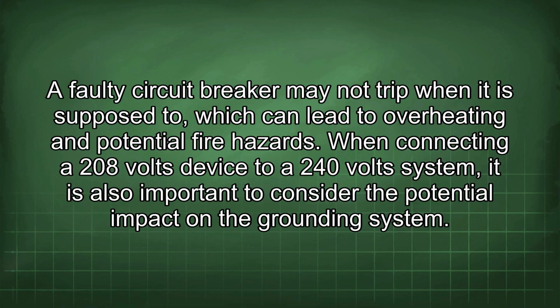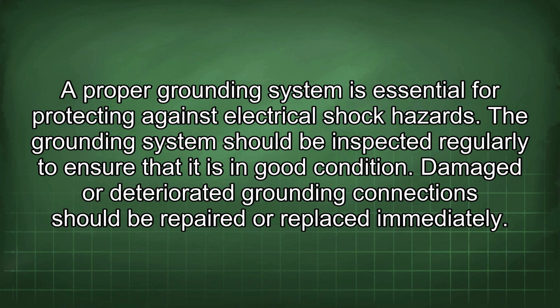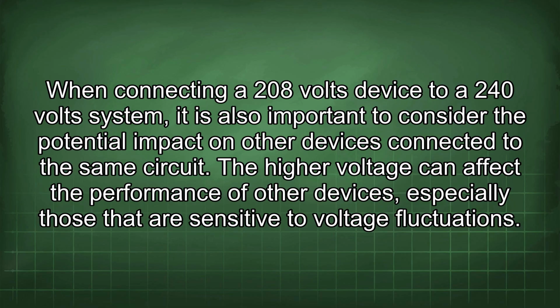hazard. When connecting a 208 volts device to a 240 volt system, it is also important to consider the potential impact on the grounding system. A proper grounding system is essential for protecting against electrical shock hazards. The grounding system should be inspected regularly to ensure that it is in good condition. Damaged or deteriorated grounding connections should be repaired or replaced immediately. When connecting a 208 volts device to a 240 volt system, it is also important to consider the potential impact on other devices connected to the same circuit.